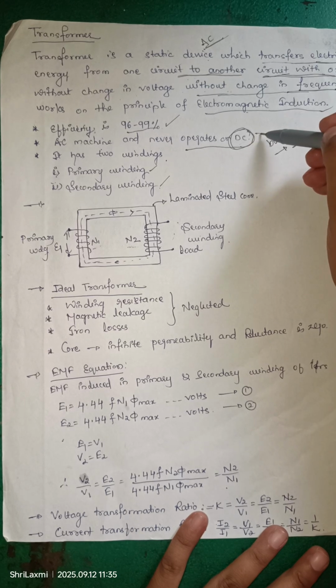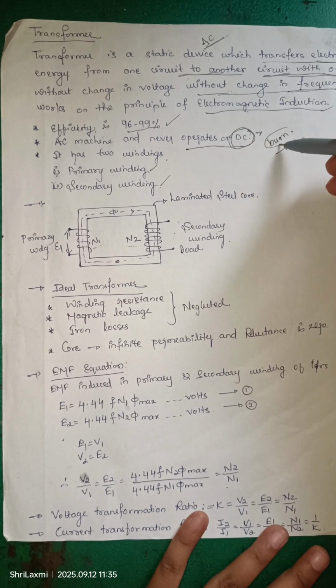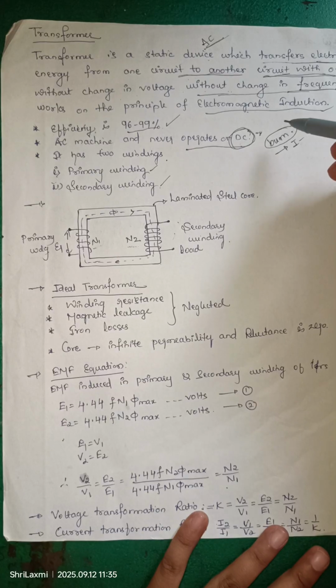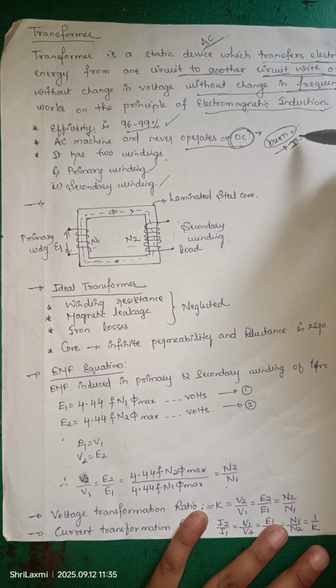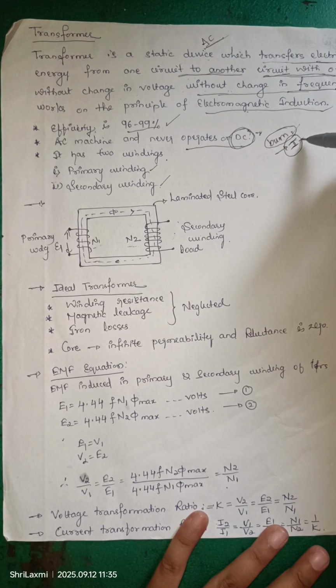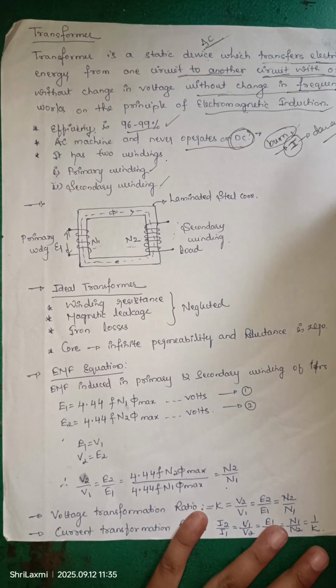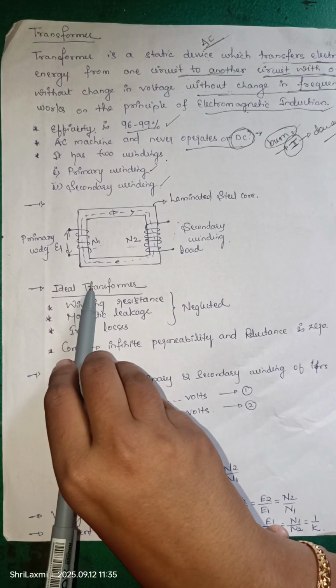If you try to operate it on DC, the windings will get burned due to a heavy inrush of current inside the transformer, and this leads to damage of the transformer. Now let's look at the pictorial representation of the transformer.